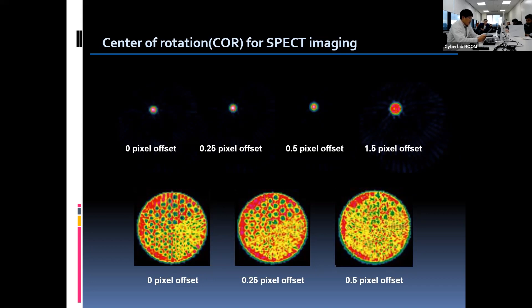The images on the bottom are reconstructed slices of a Jaszczak phantom image. Images obtained with 0.25 pixel offset error show slight degradation compared to those with no offset error. On the contrary, significant degradation is seen in the image with 0.5 pixel error. As we see from these examples, COR offset error causes a loss of reconstructed spatial resolution and contrast. In this case, correction for COR offset error must be done immediately.